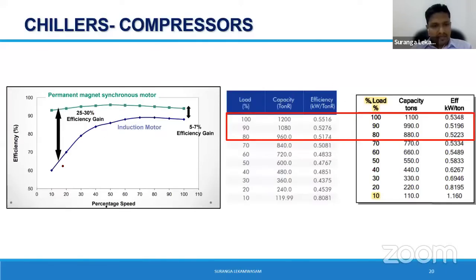Some reference I have included here. Compared with induction motors, you can see that the efficiency of the permanent magnet synchronous motor used in maglev chillers doesn't drop at part loads, whereas it drops drastically in induction motors, right? So you can understand that induction motors or conventional chillers are not good in this range, whereas these somewhat sustain their efficiency in the low capacity range.